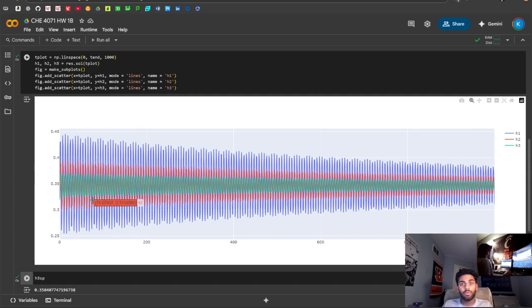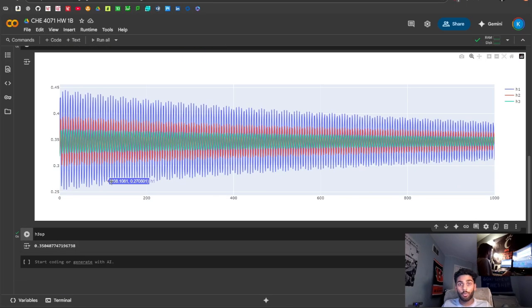So the two things that we look at when we are controlling the controller gain is we look at the proportional offset, which is how much the offset of where this oscillation settles at is from the desired set point that we set by the control, as well as the stability of our system. Does it converge within a reasonable amount of time at the proportional offset value? Are we diverging to infinity because our gain is too high? These are two things that we want to keep in check when we are designing controllers for process automation.